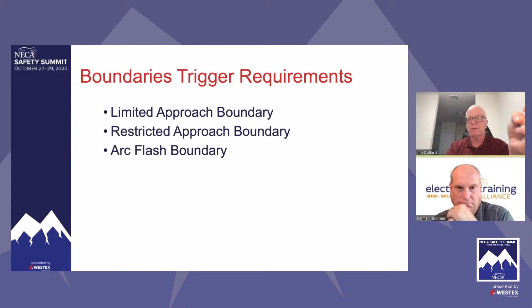There are two types of risk assessments: shock risk assessments in 130.4, arc flash in 130.5. And in any shock risk assessment, what's step one? Identify any shock hazards. Two, estimate the likelihood of occurrence of injury or damage to health and the potential severity. Three, determine if additional protective measures are needed. And if they are needed, we know we have to go back to the hierarchy of risk control. And number one is eliminate. That always has to be the first thing that we consider.